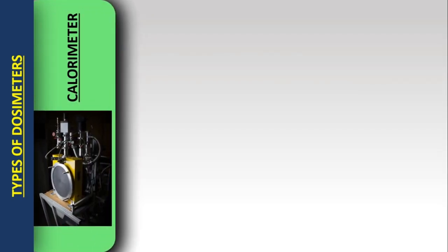Moving forward to the types of dosimeters. First we have the calorimeter. A calorimeter is a device used to measure the change in temperature. The basic assumption is that when an object is irradiated, all the absorbed dose will appear as heat. So the measurement of temperature change refers to the measurement of absorbed dose.